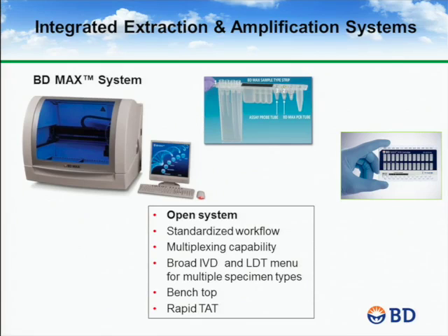And the advantage of this system, in contrast to all of the systems I've shown before, is that it can be used to do processing of assays developed, in this case by Becton Dickinson or by one of our commercial partners. But in addition, it can be used to do processing of samples or tests that were developed in your own laboratory or in one of your colleagues' laboratories, and that's been migrated onto this platform.